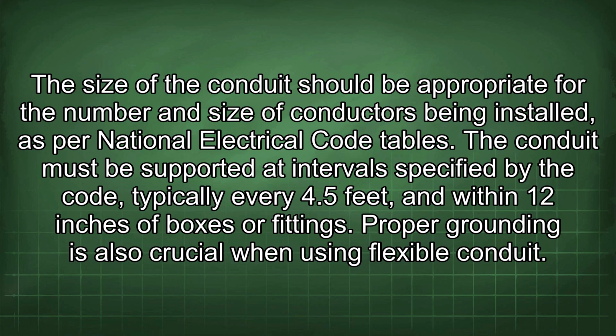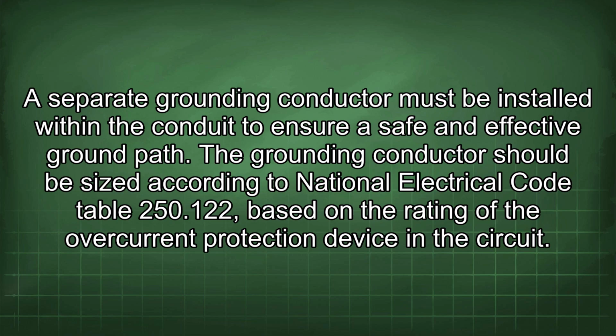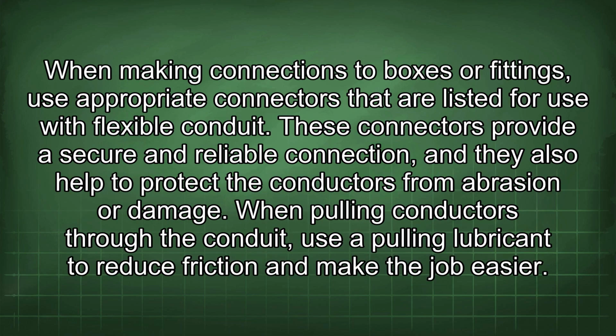Proper grounding is also crucial when using flexible conduit. A separate grounding conductor must be installed within the conduit to ensure a safe and effective ground path. The grounding conductor should be sized according to National Electrical Code Table 250.122, based on the rating of the overcurrent protection device in the circuit. When making connections to boxes or fittings, use appropriate connectors that are listed for use with flexible conduit. These connectors provide a secure and reliable connection, and they also help to protect the conductors from abrasion or damage.